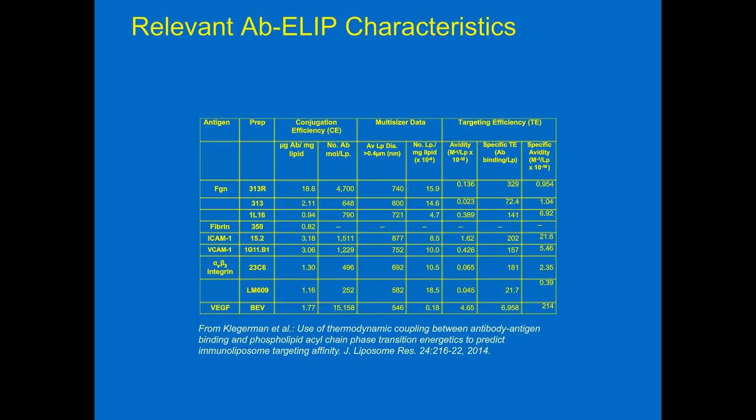Most of this has been automated, so that if your aperture gets clogged, it'll just unclog it automatically for you. But you have to be careful. You have to work with very clean preparations and clean solutions to get around that. In terms of being able to enumerate and size at the same time to great detail, the Multisizer is probably the best instrument we've worked with.